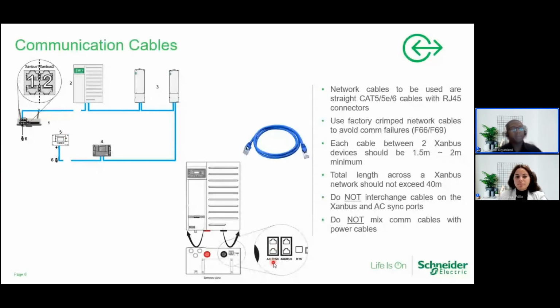You have two here, and everything is daisy chained. So let's assume you have two inverters. From inverter number one to inverter number two, you're going to only make use of one of the AC synchronization ports. The other ports are going to be left open. You're not going to put anything there. If you have three inverters, from one of the AC sync ports of the first inverter to the second inverter, then the other port of the second inverter to the third inverter. So one port on inverter number one and another port on inverter number three are going to be left open. And it doesn't matter which one you're starting from.